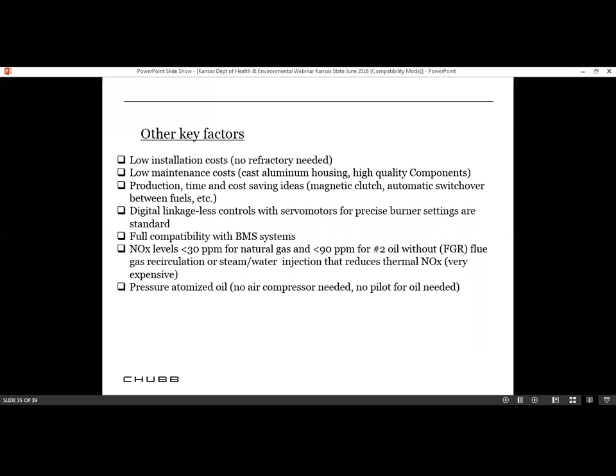Other key factors on burners is low installation cost. There's no refractory on the new burners. Low maintenance cost. The burner is made out of cast aluminum housing. Production time and cost savings. Magnetic clutch, automatic switchover between fuels. You can go from natural gas to oil without having to have a compressor or any of that other type of equipment. Digital linkage, there's no linkage. If you notice that photo I showed you, there are no linkages at all. There's servo motors that give you a precise burner setting. It's fully compatible with boiler management systems and low NOx. These burners are low NOx. They're less than 30 parts per million for natural gas, and they're pressure atomized oil. There's no air compressor, like I said earlier. No pilot for oil is needed.